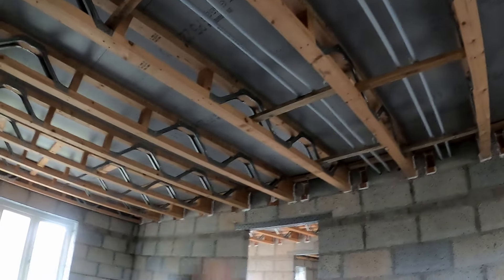There are my hot and colds for the kitchen sink. They'll be chopped in in copper in that corner, but I'll just get some speedfits across. It's just a lot quicker with them joist hanging clips because you're not trying to get a nail on top of the joist. I've clipped every one to keep them nice and supported. Got my balance in - I've run out of 22mm pipe now, but it's just going to be a 15mm hot throw into there, 22mm cold, and then a 22mm across to the bath. I've just got that bathroom there to get in and that's all the hot and colds done. And then I've only got about five or six rads to pick up upstairs anyway - I'll probably work out where they're going and then we can get all the other floor down.